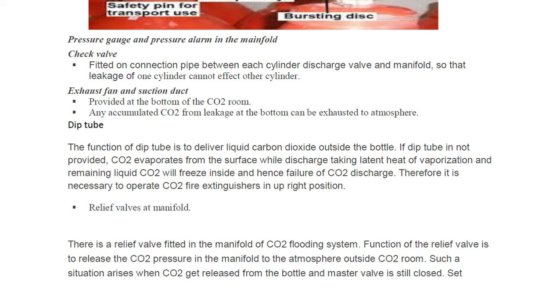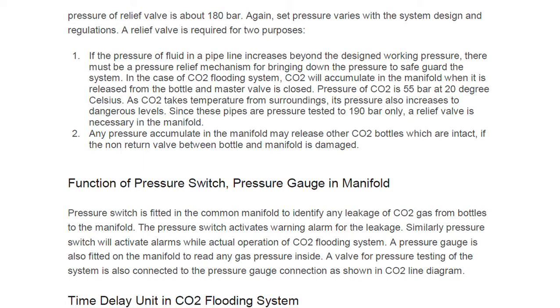The CO2 pressure in the manifold is released to the atmosphere outside the CO2 room. Such a situation arises when CO2 gets released from the bottle but the master valve is still closed. The set pressure of the relief valve is about 180 bar — this varies with the system and design. If the pressure of fluid in a pipeline increases beyond the designed working pressure, there must be a pressure relief mechanism. If the line pressure increases and the master valve is closed, the line can rupture.